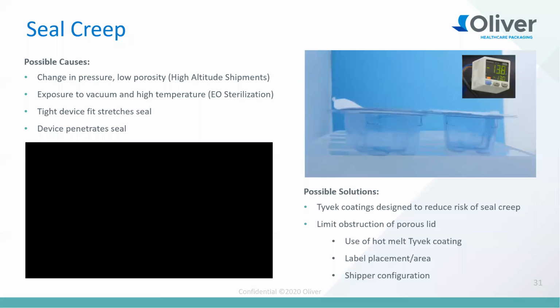Also, a few key common aspects are label placement. As you can see, the label is blocking the tray on the left that has the ultimate seal creep. Shipper configuration matters too. If you have a nice porous lid but you're overpacking it into a shipper and blocking the porosity, that could cause problems with seal creep as well.